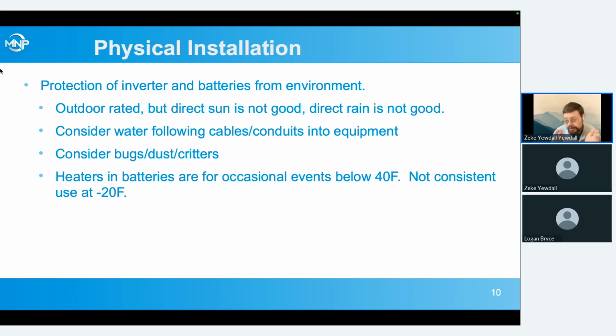It's only a 300-watt heater in each battery, and being an uninsulated cabinet, there's only so much heat that can be put in. And also, that's draining electricity from the rest of your system. If you're grid connected, maybe it just is using a little more grid power. But if you're off grid, you've got to think, so I've got a heater in there, but do I have the electricity to be running that heater all the time to make it function?